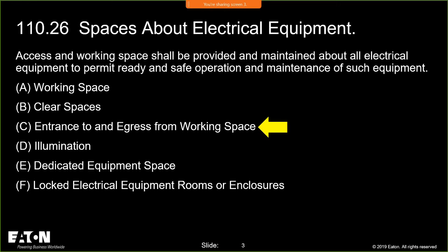They're saying the requirement shall apply to either of the following conditions: for equipment rated 1200 amps or more, which is basically what they used to have before, over 6 foot wide. But then they added, and remember, this is either of the following conditions. No, it's not both of them. It's either one. If you have service disconnecting means installed in accordance with 230.71, where the combined ampere rating is 1200 amps or more and over 6 foot wide, now you're into adding another egress. Because remember, it says for large equipment that contains overcurrent devices, switching devices, or control devices, there shall be one entrance to and egress from. So that's one entrance.